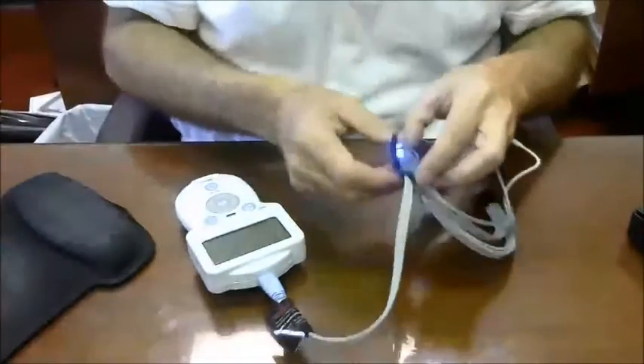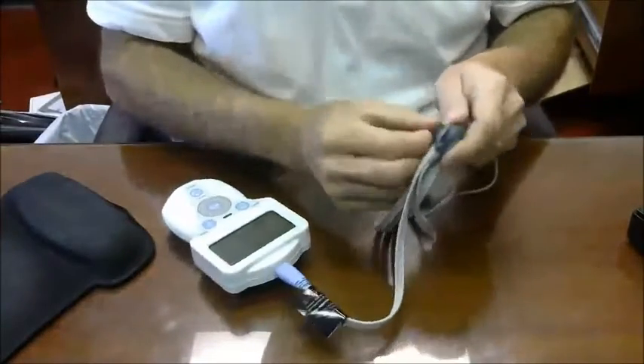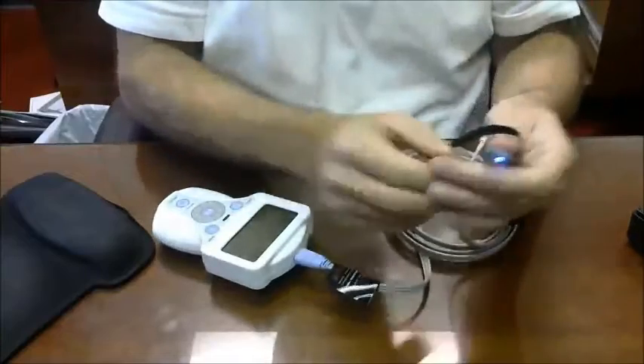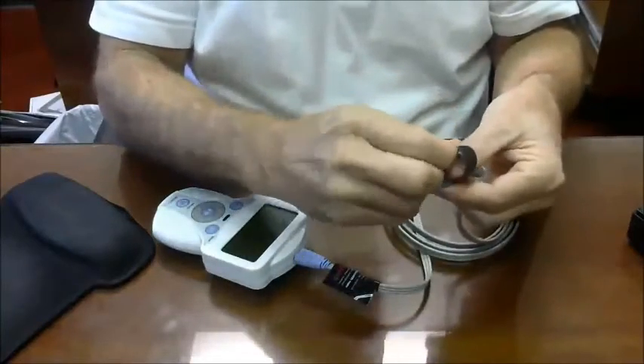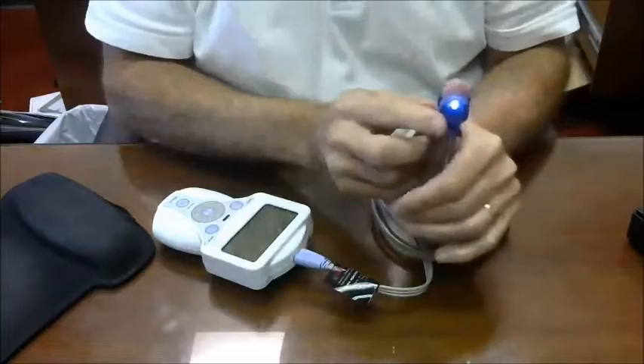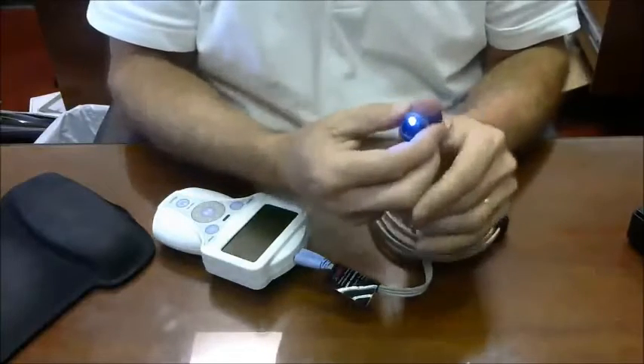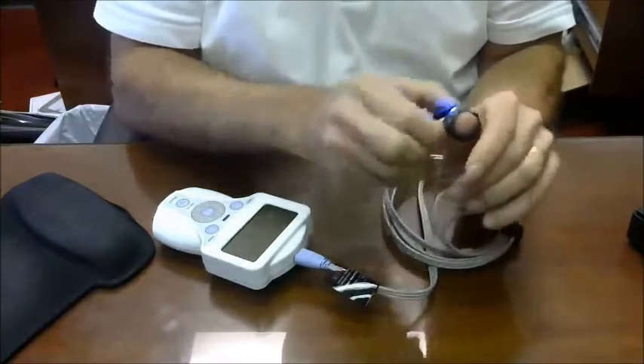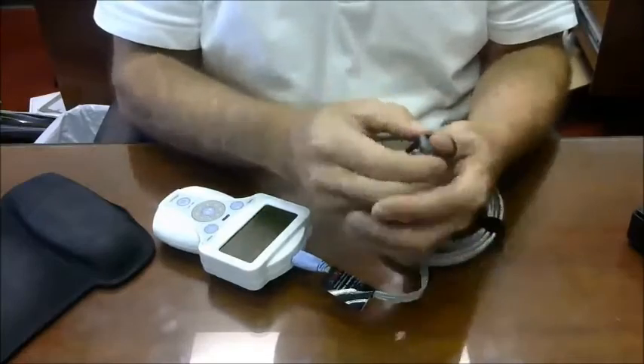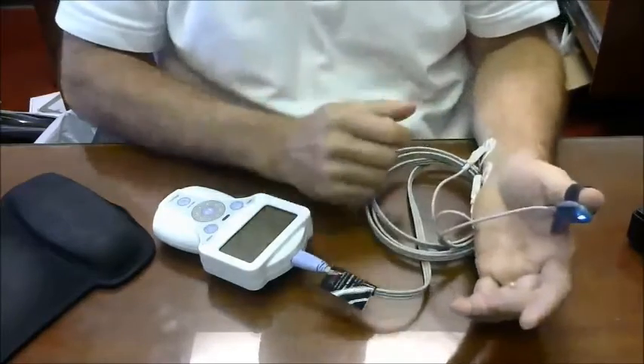So I have the electrodes thus placed, and I'm set at 30 milliamps. Then I would connect my accelerometer, which is a new cable, so I have to get this out here. I'm going to bring it down here so you see this. The nice thing about this accelerometer, because it's three-dimensional, is you can have it on the thumbprint, on the side, or on the thumbnail. It doesn't really matter as long as you're consistent on that particular patient.